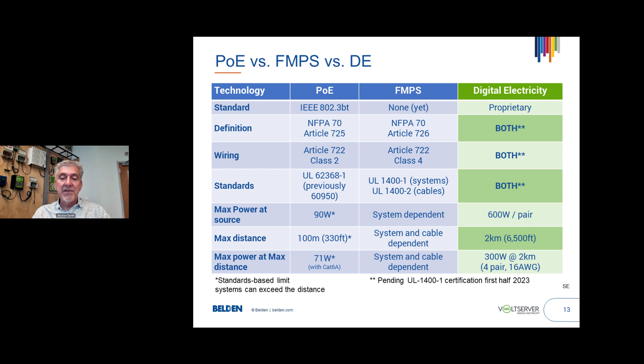So benefits of fault-managed power. As we talked about before, fault-managed power is a modernized form of electricity transmission made for digital transformation. So it installs with the same practices as Ethernet or PoE. It has lots and lots more power, about 20 times the power and 20 times the distance as PoE. So in effect, it's not really a replacement for class 2. It's a replacement for conventional power distribution. So you can power things like whole HVAC units or whole rooms of lighting, things that you would normally do with industrial level power. It runs thousands of feet on very skinny conductors and has system monitoring and control.